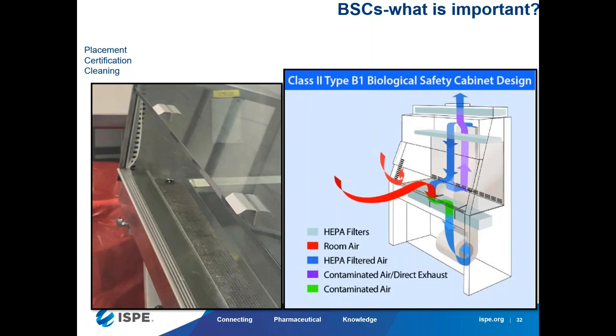But what they did, they loved using phenolic compounds, and they cleaned the BSCs with phenolic compounds. And if you know, phenolic compounds leave residues. So what did they do? They blocked the grill, which is the one that takes in outside air so it doesn't go into the BSC. So now what's happening is the outside air comes in, bounces because it's all sealed with the residue, and bounces off onto the different product. And this was an aseptically processed tissue.